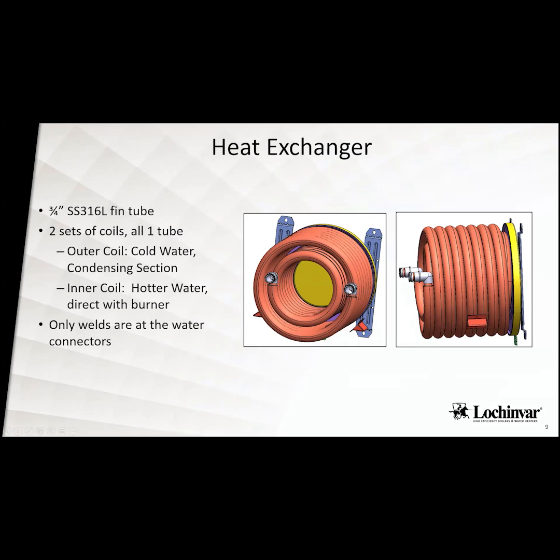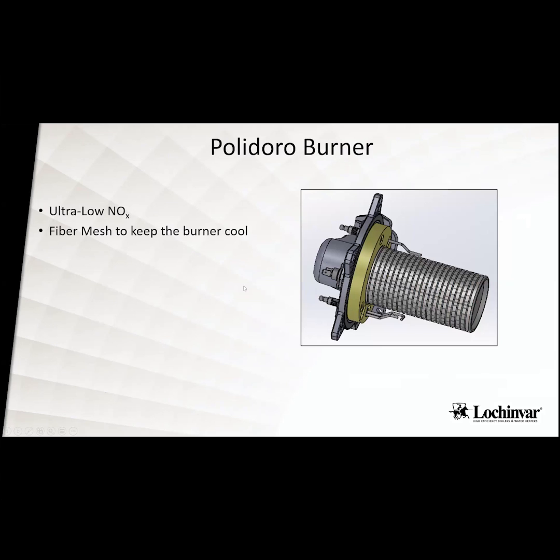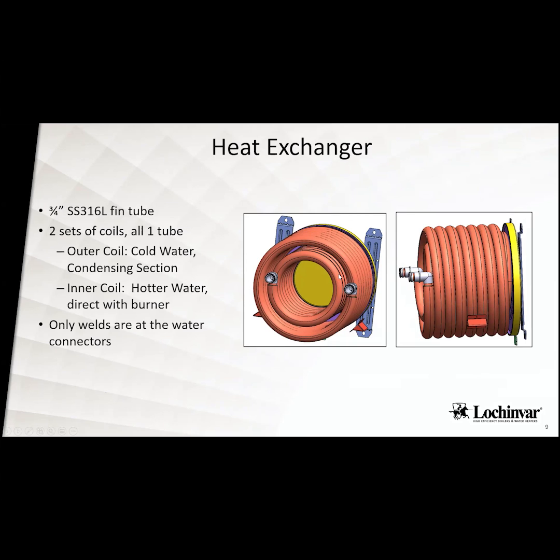So we're coming in on this one here on the right side. It's going around the outside. We're condensing, and then it's coming back into that center and then exiting through there. So that's all 316L stainless steel with that heat exchanger. We only have 2 welds, which are right here and right here in that whole entire heat exchanger. With other primary, secondary heat exchangers, there are quite a few welds built into those heat exchangers, whereas this only has the 2 welds on it. So any questions on that heat exchanger at all?